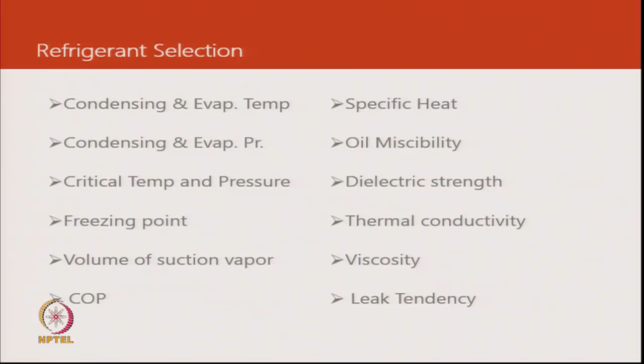Thermal conductivity leads to better heat transfer. When you look at the thin refrigerant film, which is the boundary layer inside the refrigerant tubes of a heat exchanger, a higher thermal conductivity would mean higher heat transfer. Viscosity, the lower the better, because the pressure drop is influenced by viscosity, and then the tendency to leak. Some molecules which are very, very small, like hydrogen, would tend to leak very easily and would be a concern. Along with the leak tendency is also how easily we can detect the leak. Do we have equipment that can help us pinpoint the origin of the leak and repair it, both during manufacturing as well as in service?